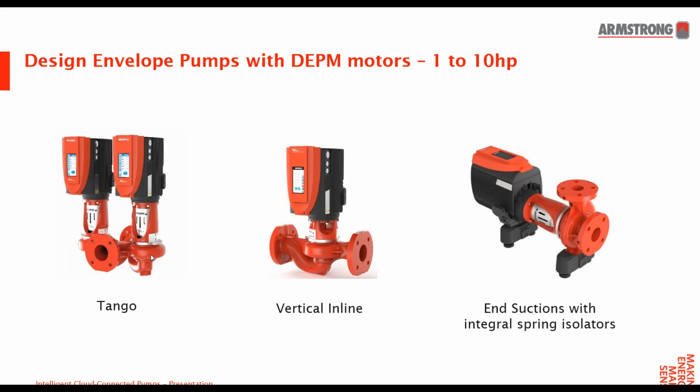In many instances, that's extra cost and materials and labor for all of that wiring. And then also when you wire it directly so close to the motor, you don't have to worry about many of the reflected wave issues that you might see with other installations. As the drive and the motor get further apart, you might get an effect called reflected wave voltage. If you get more than 100 feet apart between the motor and the drive, you can get issues, and then you would require additional accessories to mitigate that type of reflected wave voltage and the damage you would see with that.